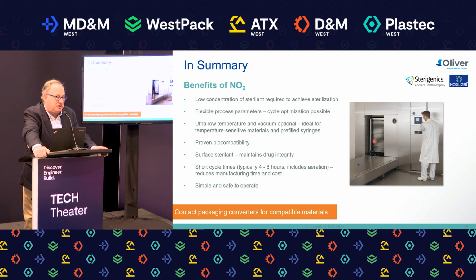In the case of implants or a vial, it's just external residuals. We're not doing internal residuals, but we do the residual analysis coupled with the worst case part of that study. And as far as timing is concerned, for lethality we typically have a 14-day grow out of the BI after we run our cycles, and we like to repeat that once we've identified a good lethal cycle. For the worst case application, typically that runs 30 days after worst case. So with availability of product, understanding that we can come to a lethality cycle relatively soon, we're looking at a 60-day process.